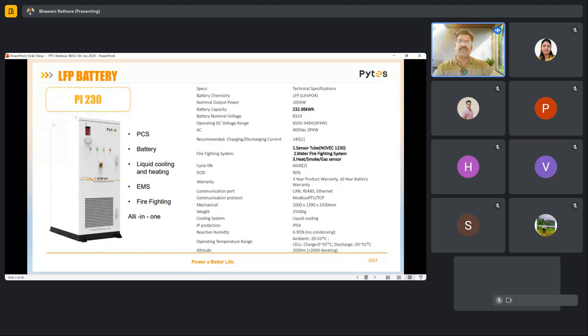In form of AC basically, DC 650 to 949. Recommended charging/discharging current 140. Firefighting system is also shown. Cycle life is 6,000, DOD depth of discharge 90%, with warranty, and without disturbance of efficiency we can discharge up to 90%. Warranty is 3 years.